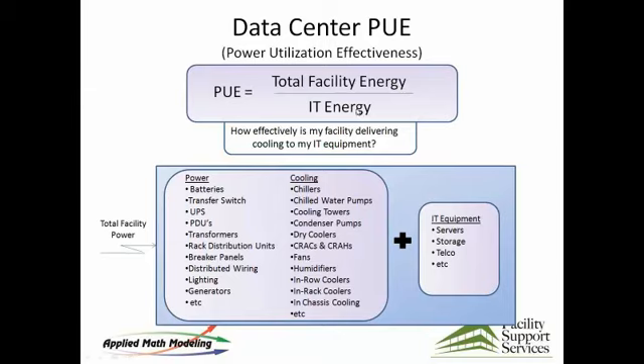You have to remember that in some cases you're talking about megawatts of data, and the consumption of electricity in a large data center can be in the range of $500,000 a month. So this is a lot of money that we're talking about here, and the opportunity to reduce it by 25–30% is quite good. Now, you want to have a low PUE, of course, because we're measuring the ratio of total facility power in the numerator compared to IT power. So you'd like to drive that thing to 1. If you could drive it to 1, it means that you're only powering the IT equipment alone, and you don't have to pay for anything else.